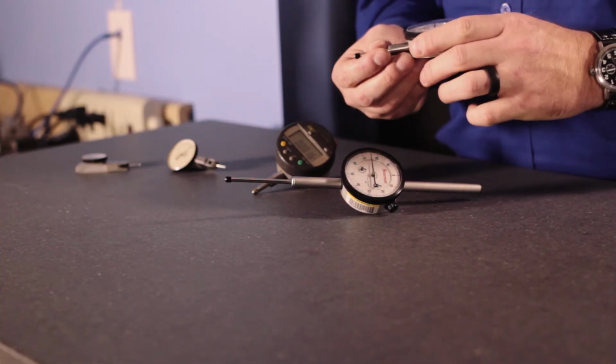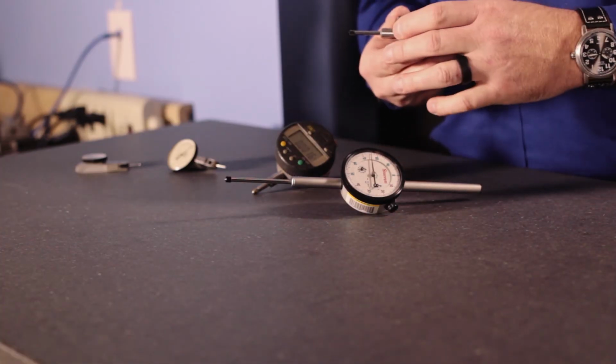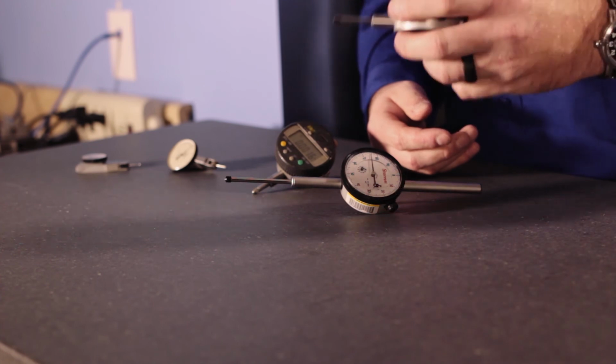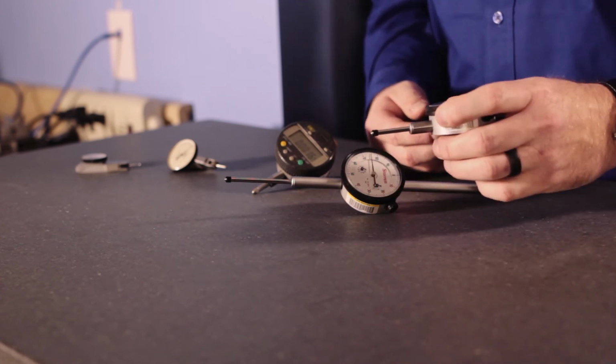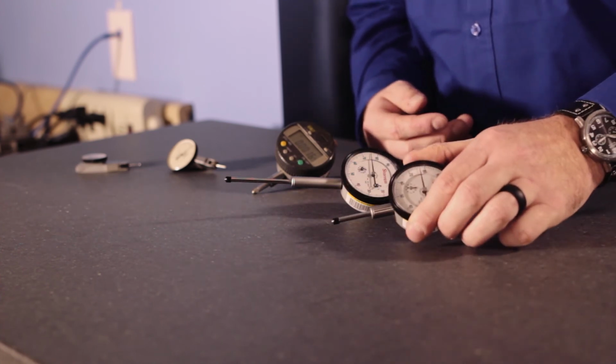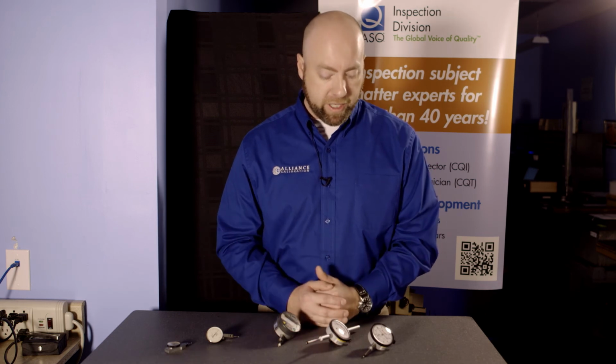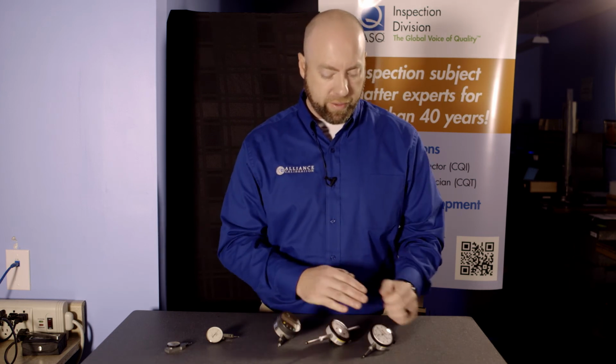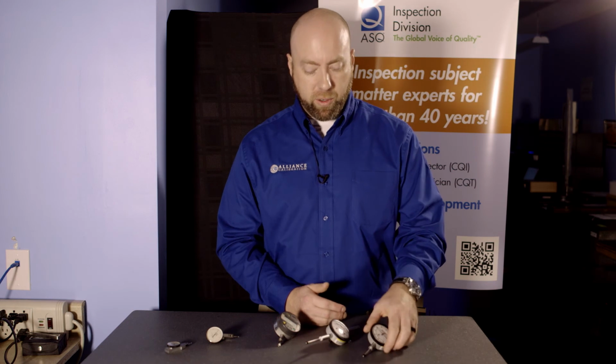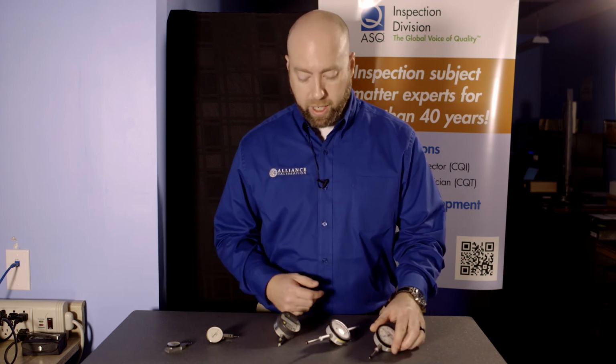What you're going to do is make sure that you're handling them gently. You're going to mount them gently. You'll set them in their cases or their storage places gently and make sure they're protected at all times. Cleaning them, again, just a mild cleaner. Usually you can get away with just toweling them off with a lint-free towel, making sure everything is wiped off and clean, making sure that no debris gets up inside of the travel of the stem. The same with all the indicators. Just keeping them clean is incredibly important.